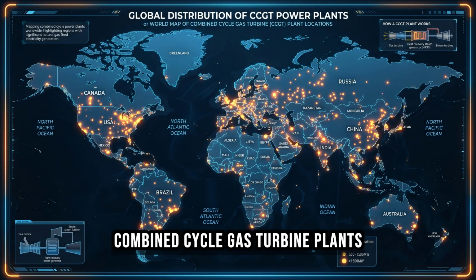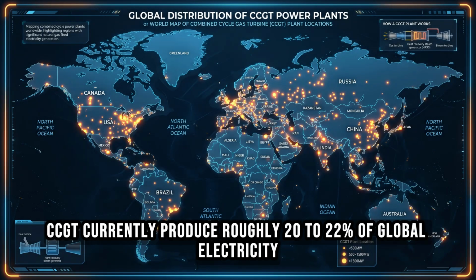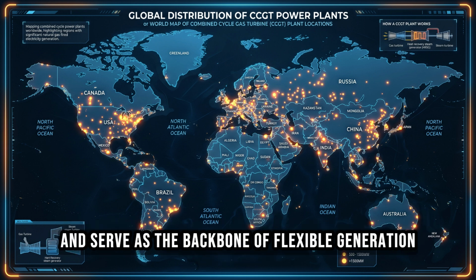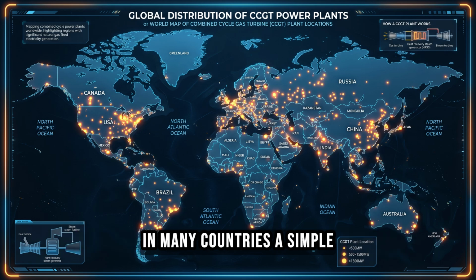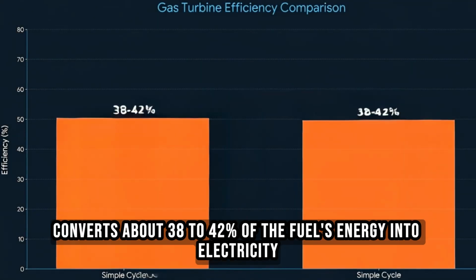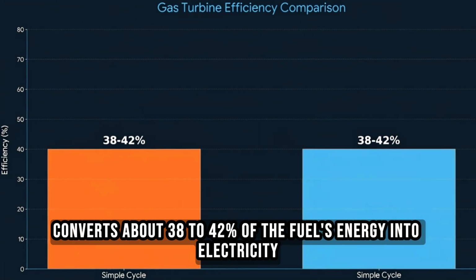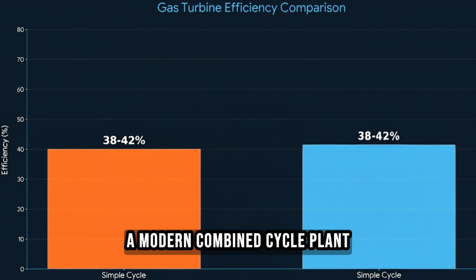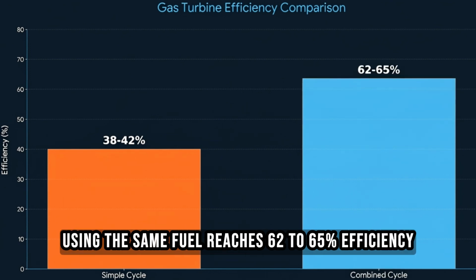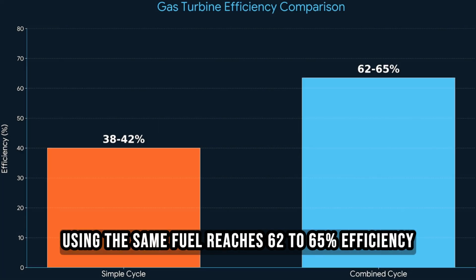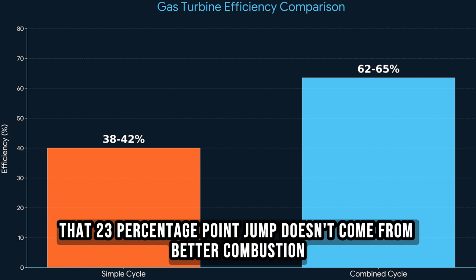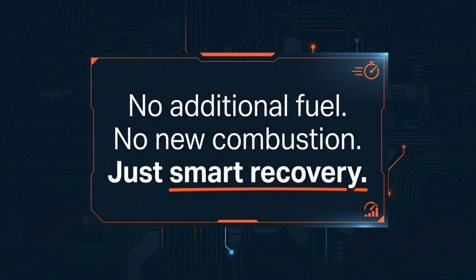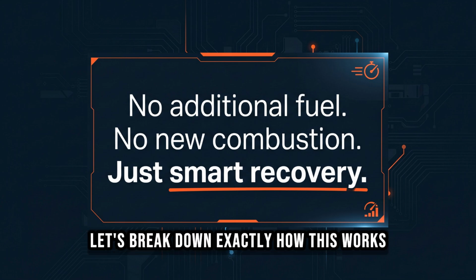Combined cycle gas turbine plants, CCGT, currently produce roughly 20 to 22% of global electricity and serve as the backbone of flexible generation in many countries. A simple open-cycle gas turbine converts about 38 to 42% of the fuel's energy into electricity. A modern combined cycle plant using the same fuel reaches 62 to 65% efficiency. That 23 percentage point jump doesn't come from better combustion. It comes from not wasting the enormous amount of heat that the first turbine already created. Let's break down exactly how this works.